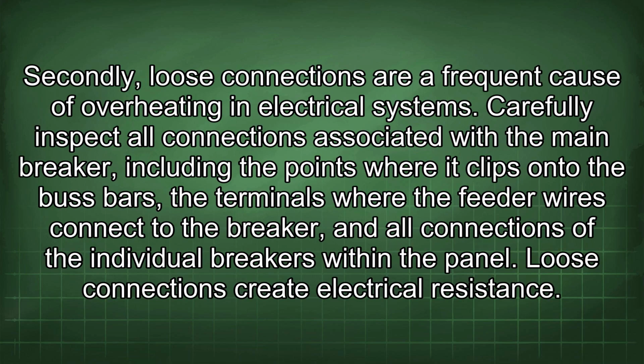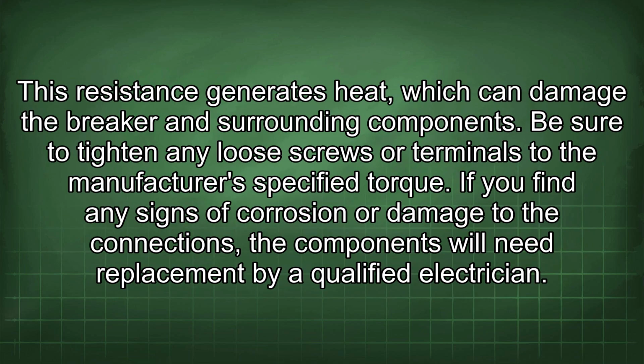Secondly, loose connections are a frequent cause of overheating in electrical systems. Carefully inspect all connections associated with the main breaker, including the points where it clips onto the bus bars, the terminals where the feeder wires connect to the breaker, and all connections of the individual breakers within the panel. Loose connections create electrical resistance. This resistance generates heat, which can damage the breaker and surrounding components. Be sure to tighten any loose screws or terminals to the manufacturer's specified torque.